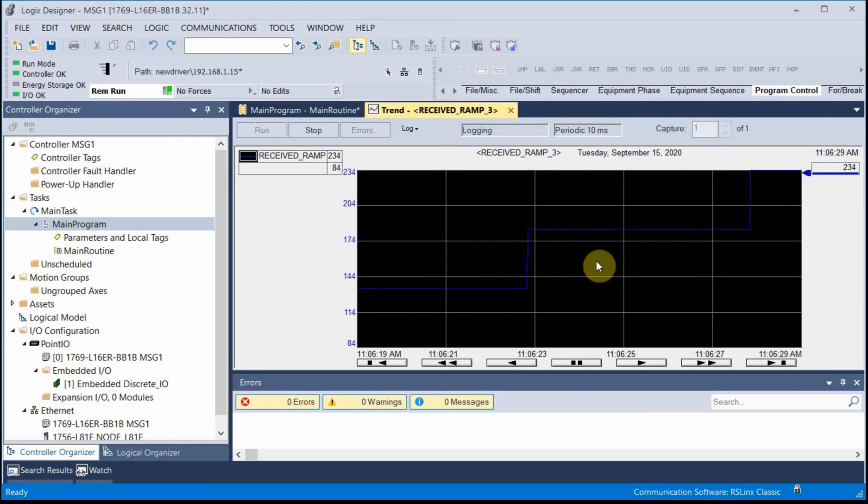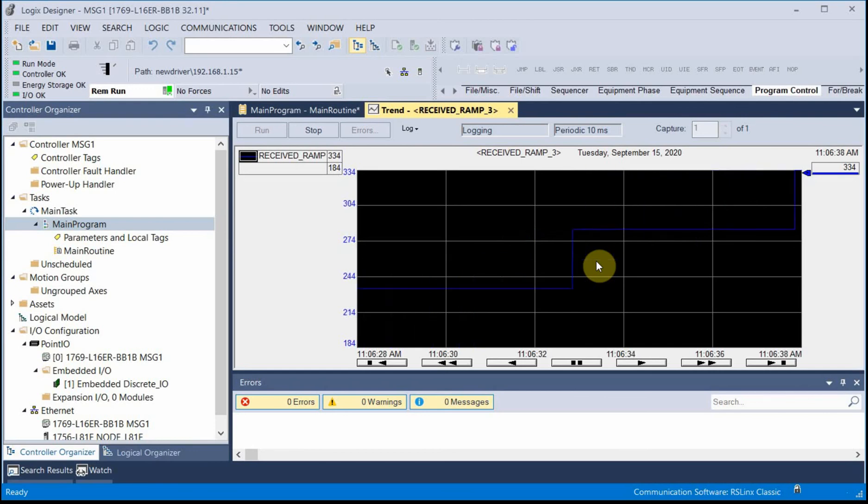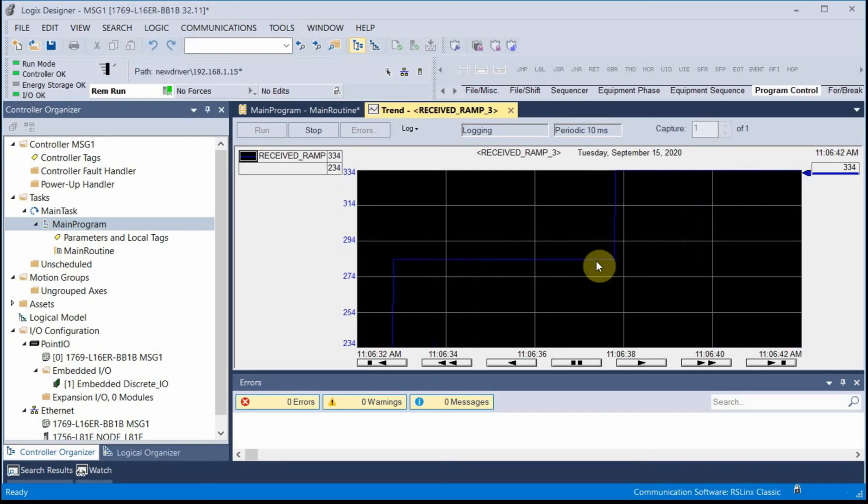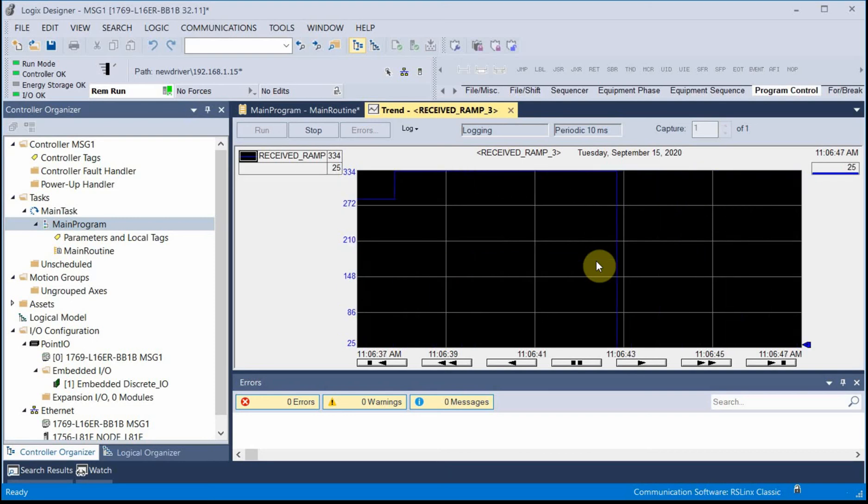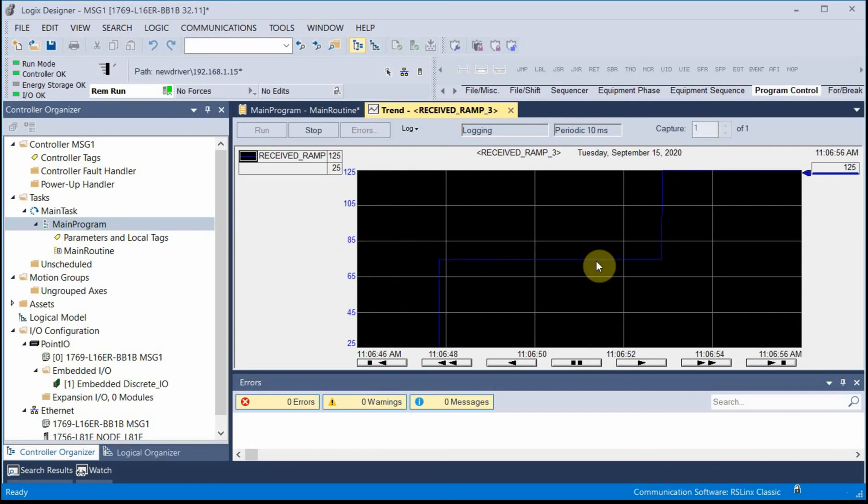The only problem is every time I poll for remote data, I give it more work to do. I give the processor work to do. I don't want to poll constantly to where it's only able to do communication activities. You'll get to a point where it will just start to either time out or just not give you accurate results. So you're going to find a balance.